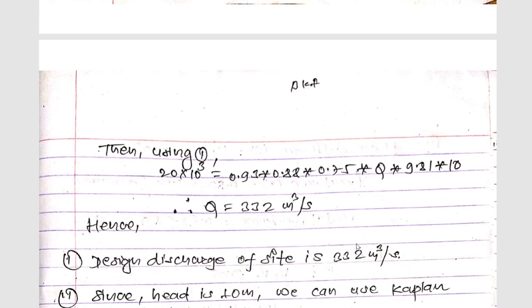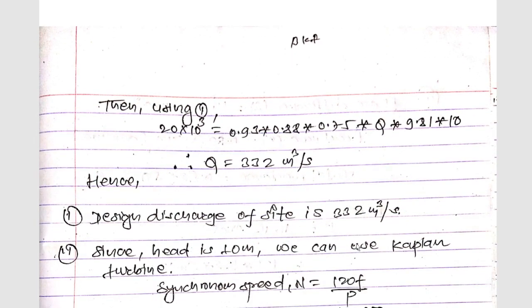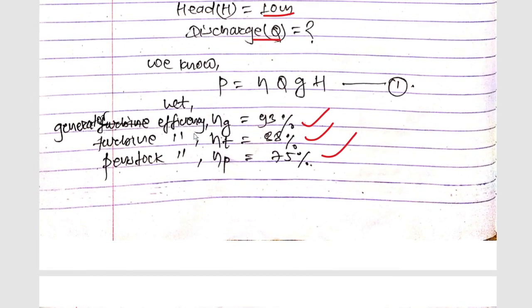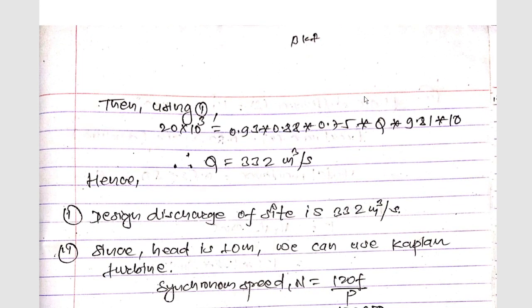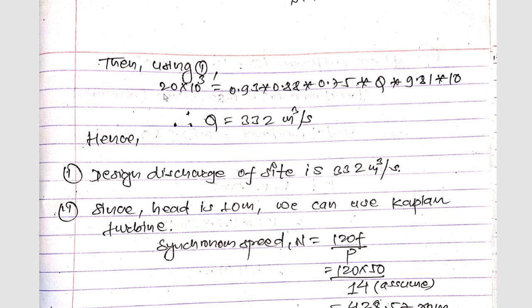Since P is given as 20 megawatts, we convert to kilowatts: 20 × 10³ kW. Our formula gives output in kilowatts. So 20,000 = 0.93 × 0.88 × 0.75 × Q × g × H, using these three assumed efficiencies.